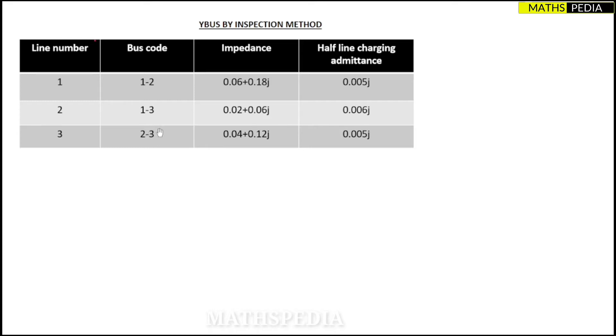In the third column, impedance or admittance will be given. Always remember: Y-bus requires all elements to be in admittance. If impedance is given, you must convert it to admittance — the reciprocal of impedance gives admittance, so take one divided by the impedance value.